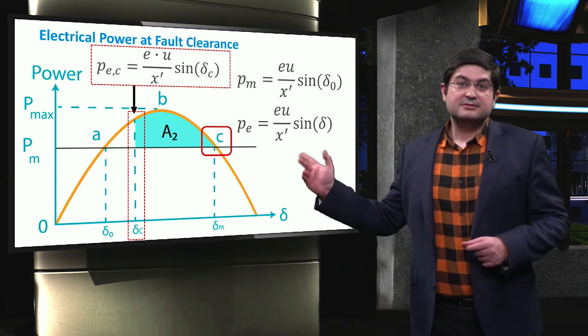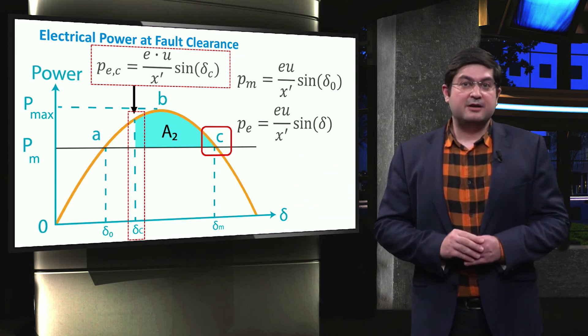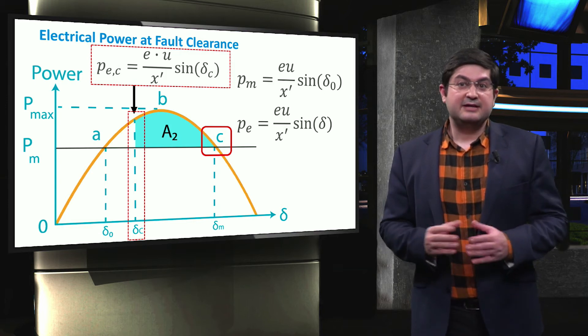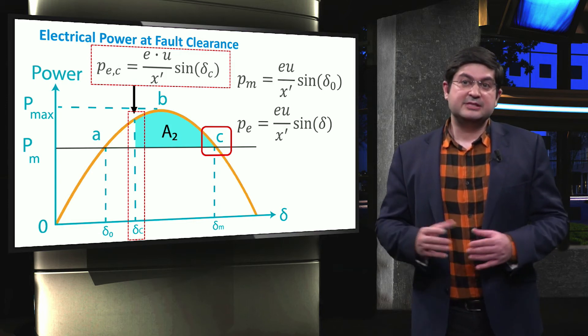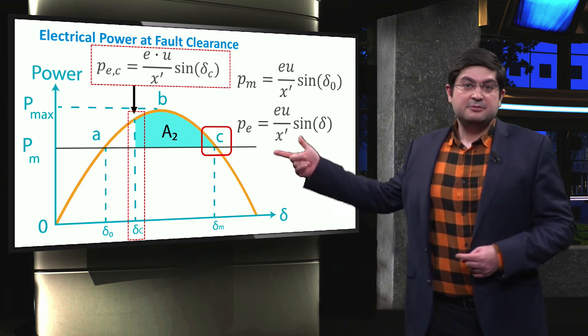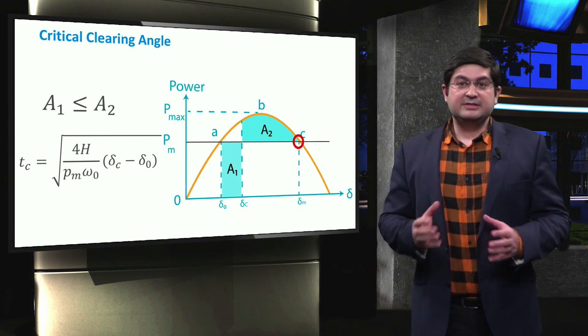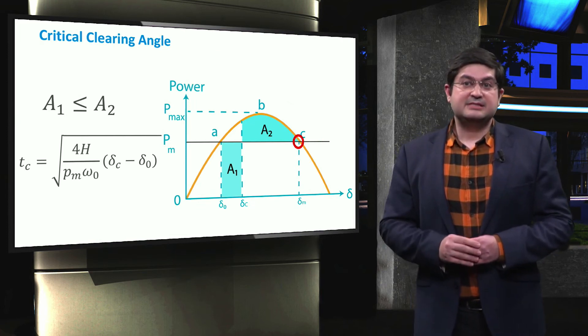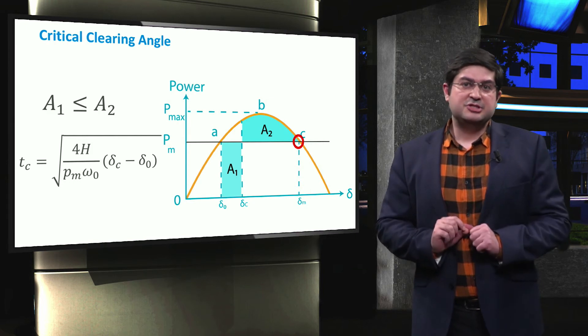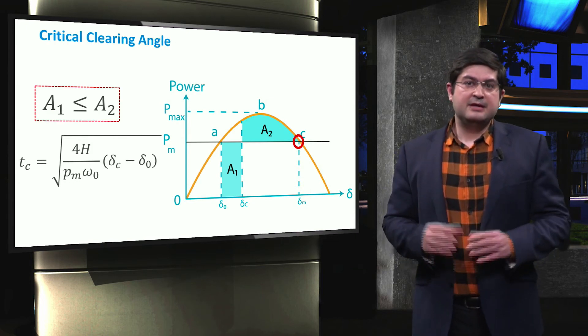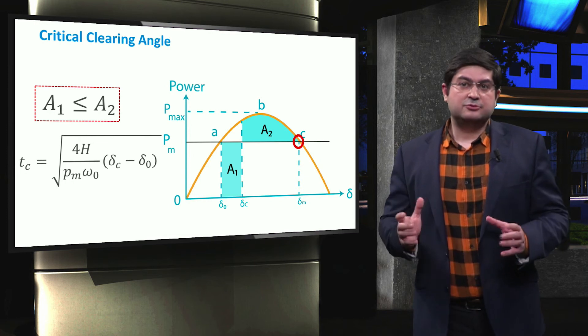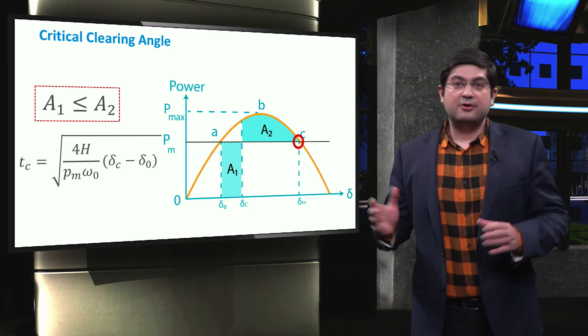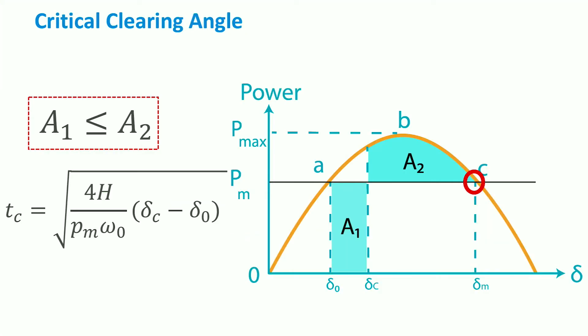Because after point C, at delta M, the input mechanical power becomes again greater than the electrical power. In this case, the rotor speed steadily increases and the machine becomes unstable. The main equilibrium criterion to keep the stability of these distributed generators based on electrical machines is that area A2 must be greater than or equal to area A1. In other words, the deceleration of the rotor in area A2 shall be large enough to cancel out the acceleration in area A1.